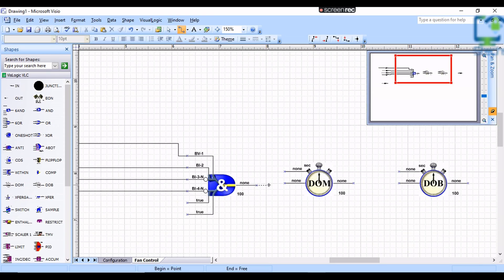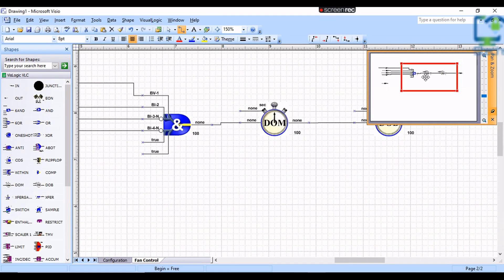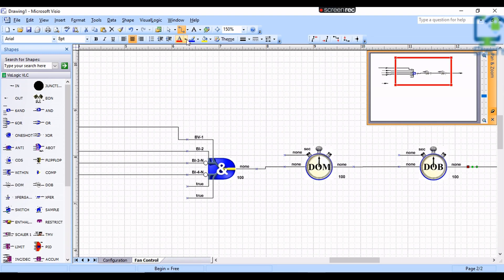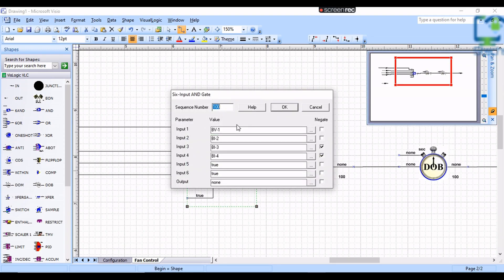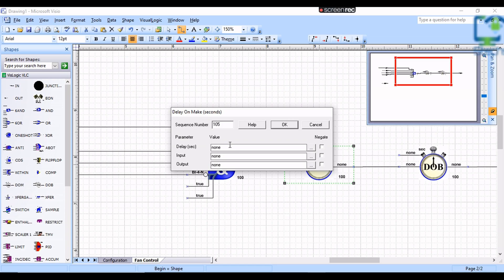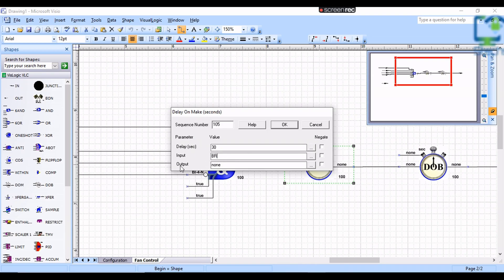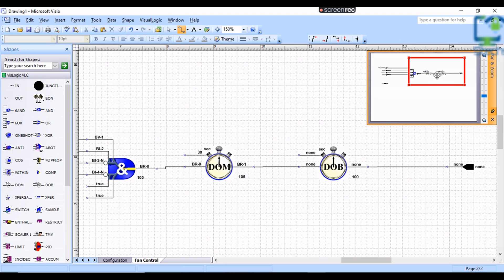Now I am going to link these functional blocks as shown in the video. I need to change the sequence number of the functional blocks. The 6-input AND gate sequence number is 100, and I am going to give the timer block next to it 105. For that, double-click on the timer functional block, change the sequence number to 105, and set the delay to 30 seconds as per the sequence of operation. I need to add input and output branches. I am going to give BR 0 in the input and BR 1 in the output. We can use 8 branches on one page.